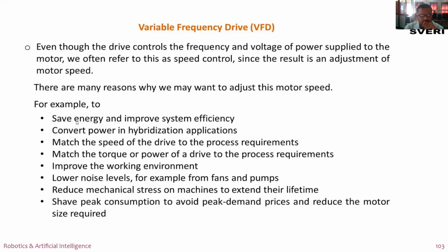For example, to save energy and improve system efficiency, convert power in hybridization applications, match the speed of the drive to the process requirements, match the torque or power of a drive to the process requirements, improve the working environment, lower noise levels, for example, from fans and pumps, reduce mechanical stress on machines to extend their lifetime, shave peak consumption to avoid peak-demand prices and reduce the motor size required. Therefore, this is the variable frequency drive. We'll see its video also.